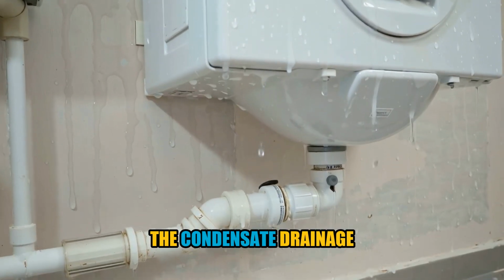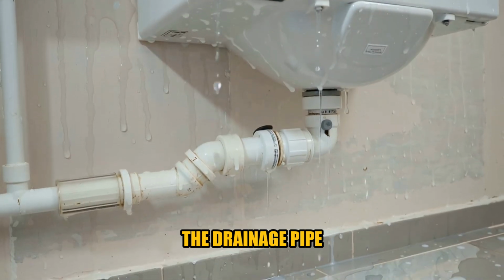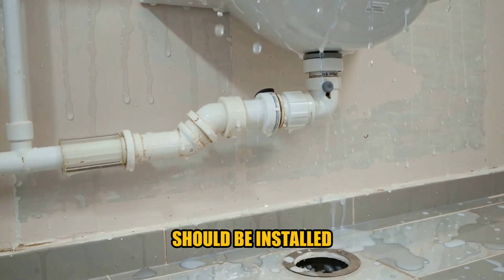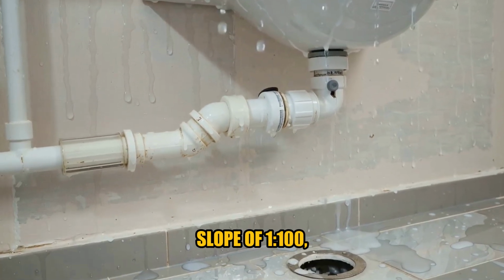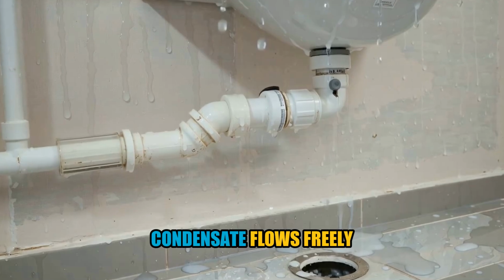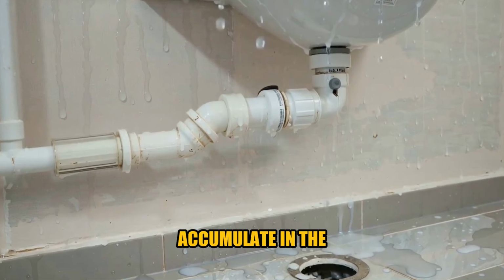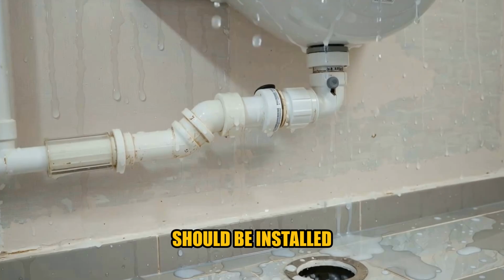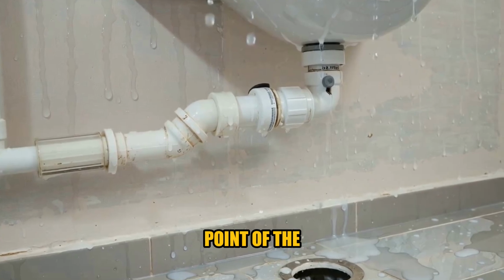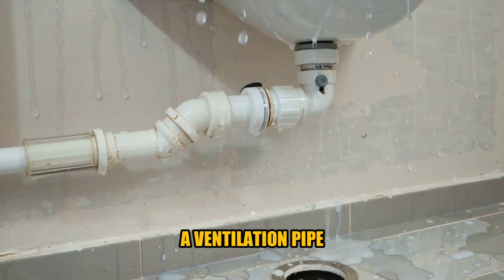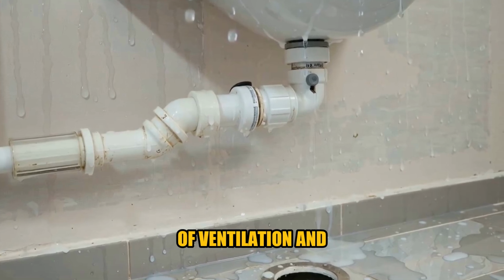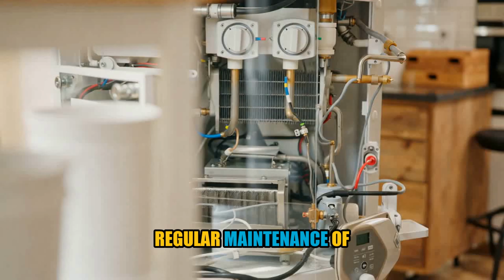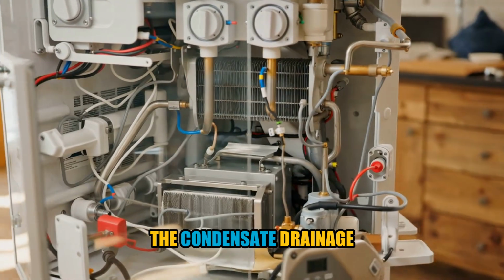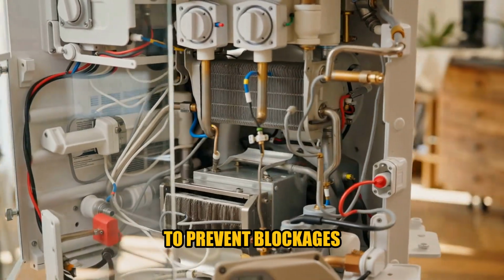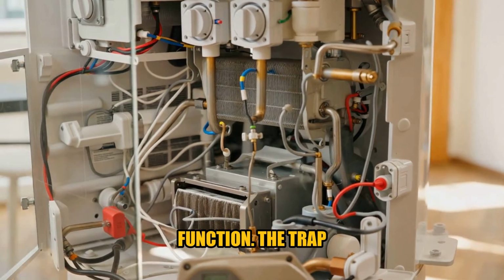Proper installation of the condensate drainage system is essential. The drainage pipe should be installed with a minimum slope of 1 to 100, ensuring that the condensate flows freely and does not accumulate in the pipe. The trap should be installed at the lowest point of the drainage system, with a ventilation pipe providing a means of ventilation and preventing siphoning. Regular maintenance of the condensate drainage system is necessary to prevent blockages and ensure proper function.